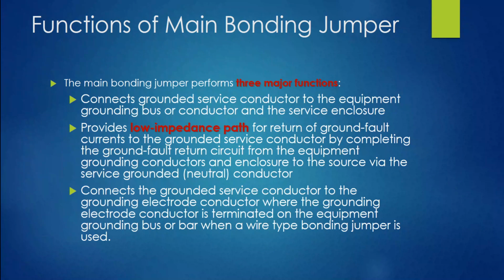Also, it connects the grounded service conductor to the grounding electrode conductor, where the grounding electrode conductor is terminated on an equipment grounding bus or bar where a wire-type bonding jumper is used. Remember that one, because I'll show you that in a minute. Again, as you saw earlier, it's that wire that connects the two buses. If that's the orientation you choose on your installation, rather than putting everything on the same bus, then once you size that wire type, you can bring the grounding electrode conductor to that equipment grounding terminal bus, provided that you use a wire type bonding jumper or bus bar. Okay.